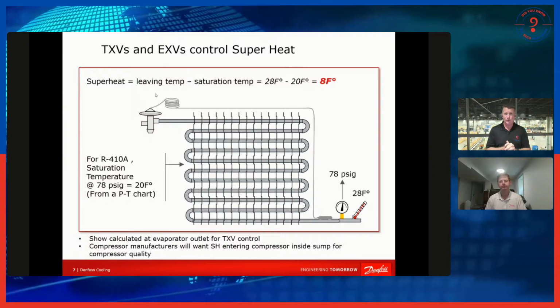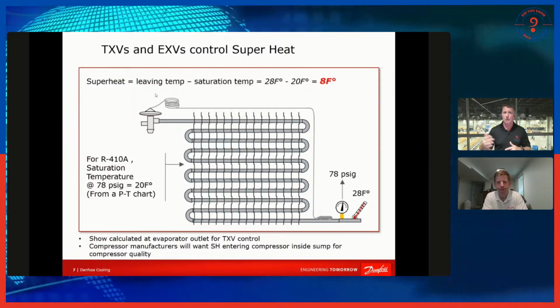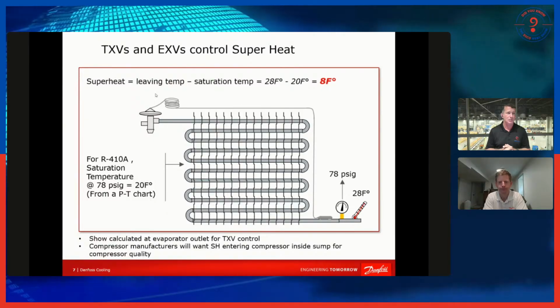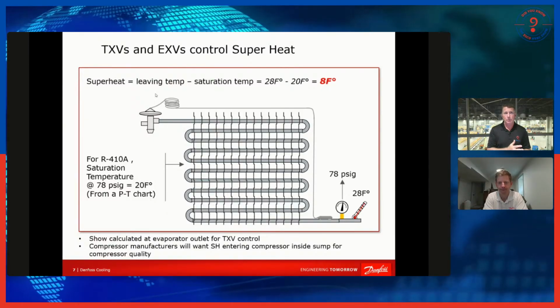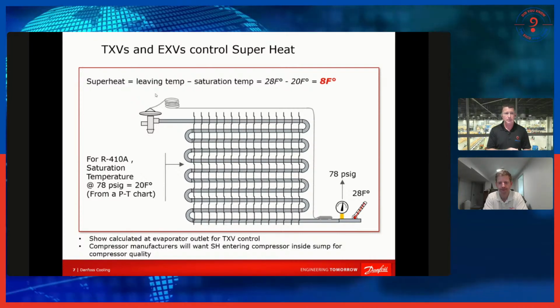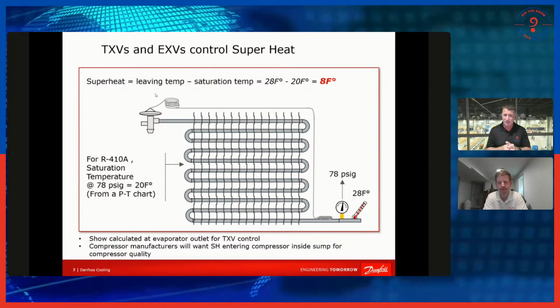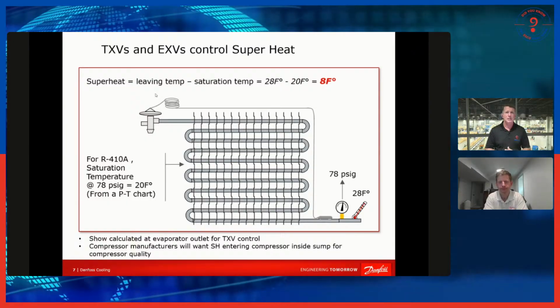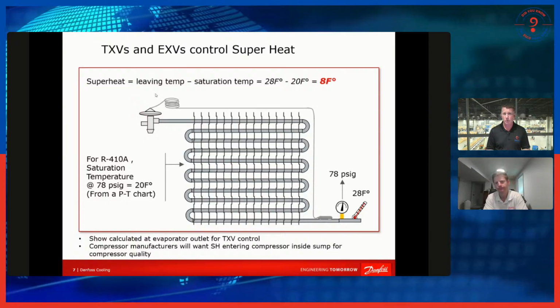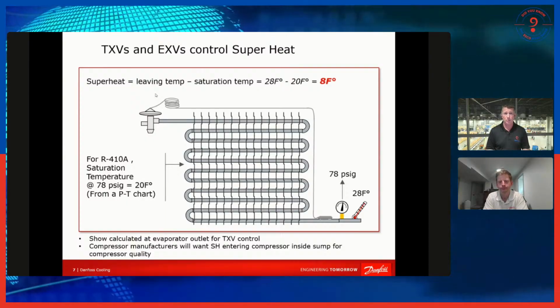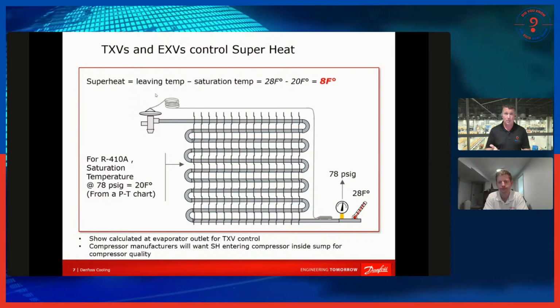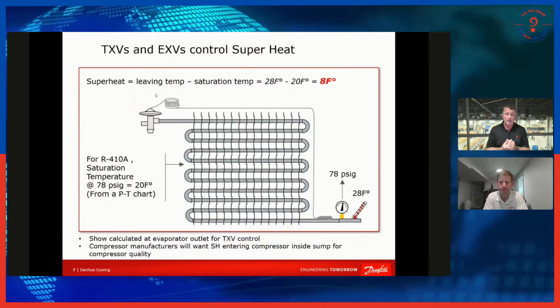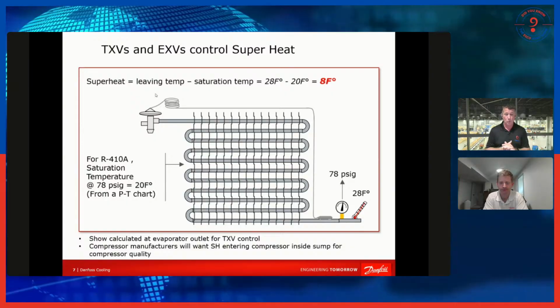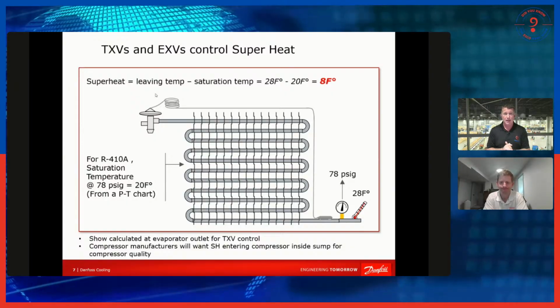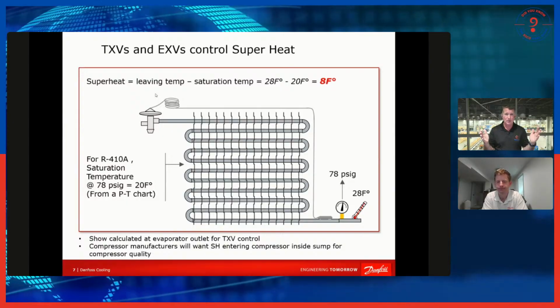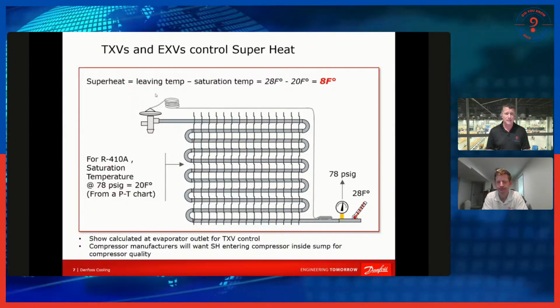I've seen a big change over the last decade in residential, commercial split systems, even package units, RTUs. We saw a lot of adjustable thermostatic expansion valves up until a decade or so ago, and then I've noticed a lot of our equipment has been using fixed thermostatic expansion valves. With those fixed valves, we're also assuming that the system is tuned properly for the system we're working on. And unfortunately, there is no control of those. Where they come is where they run. And many times they have a much wider float bandwidth than what we see in some of our adjustables.